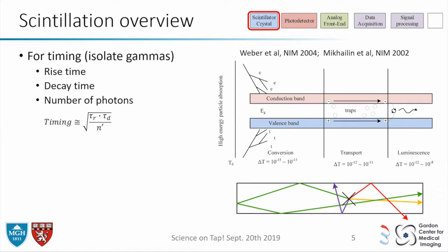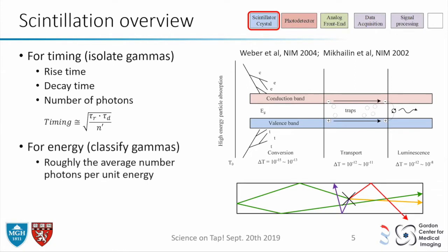Photons also travel inside the crystal, and nowadays that's something we have to look into to get performance up. For energy resolution: sometimes the gamma hits the crystal and drops all its energy at once — those are the ones we most want. But sometimes it just skips and leaves only part of its energy, then reaches another area in the scanner. Because we know those have only partial energy, we can throw them out or keep them. Keeping them improves sensitivity but blurs the image — it's a trade-off.